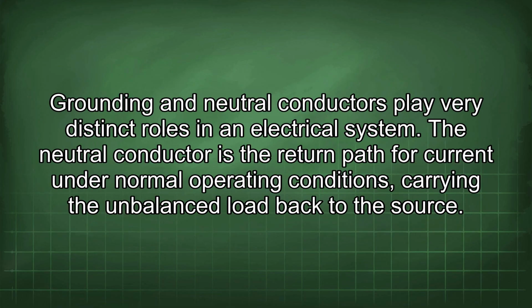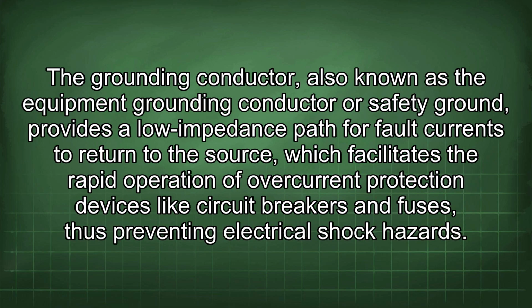Grounding and neutral conductors play very distinct roles in an electrical system. The neutral conductor is the return path for current under normal operating conditions, carrying the unbalanced load back to the source. The grounding conductor, also known as the equipment grounding conductor or safety ground, provides a low impedance path for fault currents to return to the source, which facilitates the rapid operation of overcurrent protection devices like circuit breakers and fuses, thus preventing electrical shock hazards.